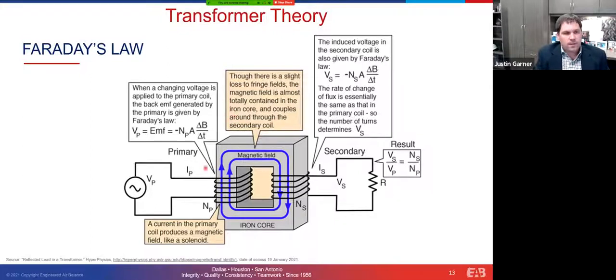But the governing principle here is called Faraday's law. What Faraday's law basically says is that an EMF is generated between a primary source and a secondary source. And that's essentially what, through flux and magnetic fields, transfers the same amount of energy, with some minor losses because of the material, over to the secondary side. And so when you simplify all this, you have this equation right here. This is the voltage of the secondary divided by the voltage of the primary, which is equivalent to the number of turns, or number of wraps around this core, of the secondary versus the number of turns of the primary. If you know the number of turns, that dictates the secondary voltage compared to the primary voltage. And this is essentially how transformers in all commercial facilities work.